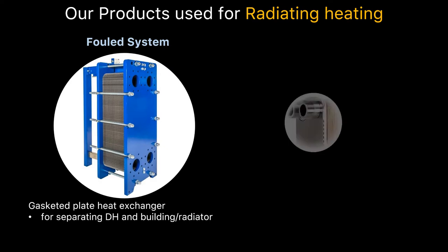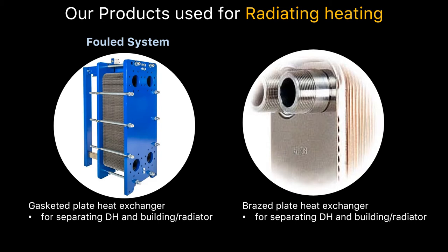We also use copper brazed heat exchangers for this kind of system. This unit is more compact, has a smaller footprint, is a cost-effective solution, and our range is optimized for HVAC applications. The water, however, must not be fouled and must be clean. Cleaning of this unit is possible when you rinse it with water.